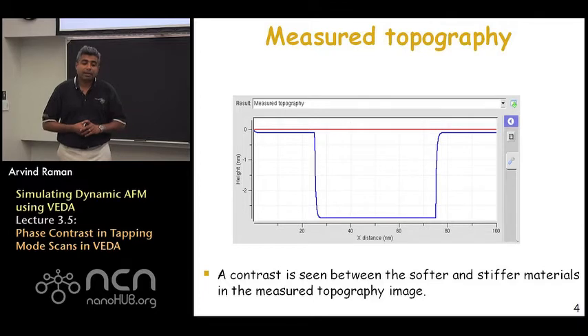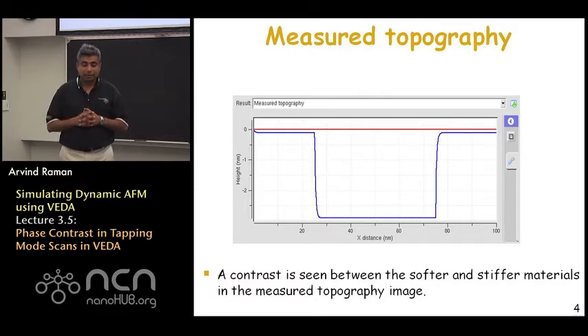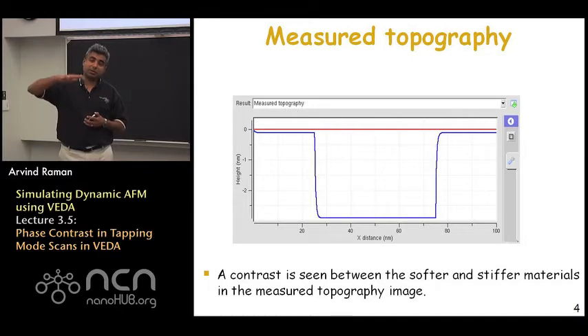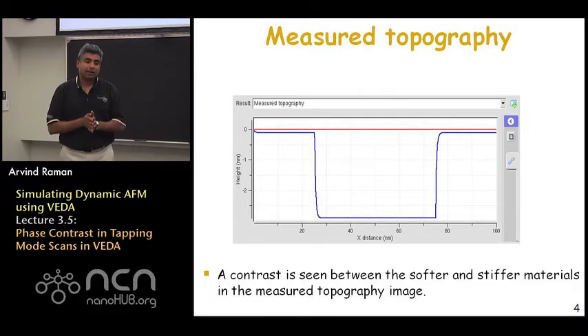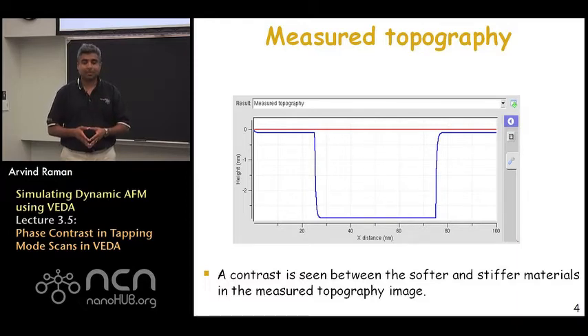Using the AM scanning tool with all the parameters given in the appendix, this is the measured topography one gets. The red shows the intended topography which is absolutely flat, and the blue shows the actual measured topography — the amount the Z motion has to change to keep the amplitude constant. Interestingly, even though the sample was originally flat and the feature was about ten times softer than the substrate, the feature appears depressed. This tells us that when we measure topography in tapping mode AFM — in dynamic AFM in general — the topography is influenced by the local properties of the sample.